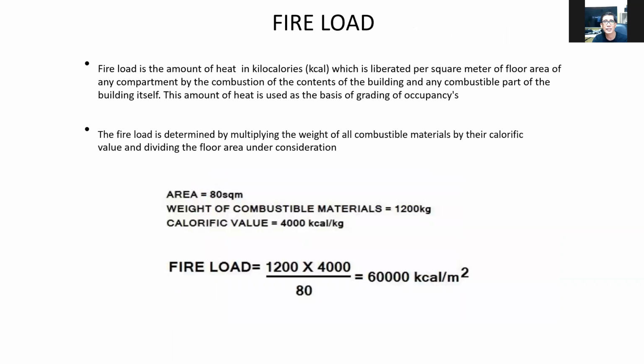So the fire load is determined by multiplying the weight of all combustible materials by the calorific value and dividing by the floor area under consideration. So if we consider this, if you have an area of 80 square meters, the weight of combustible materials is 1,200 kilograms. So you can calculate what are the materials inside the building based on actual weight, no?